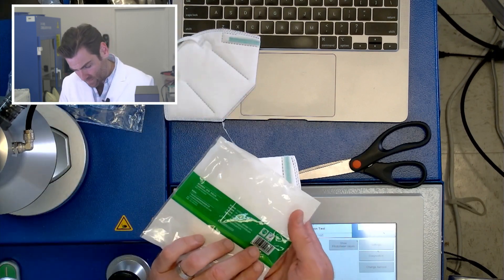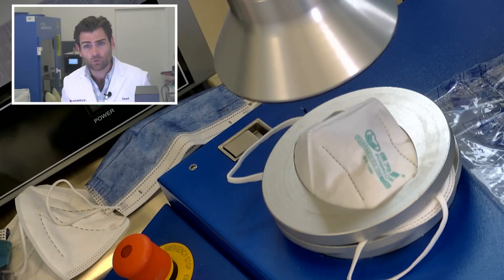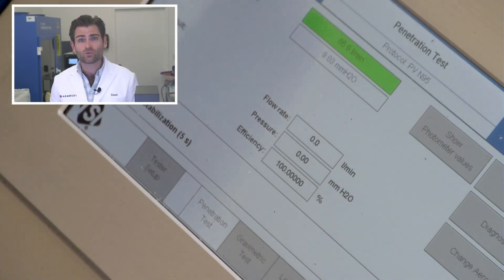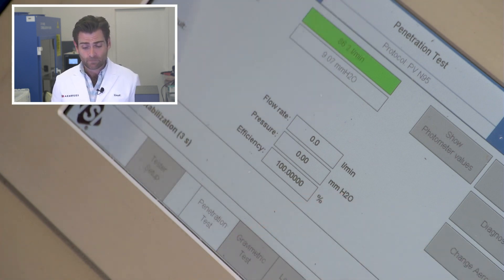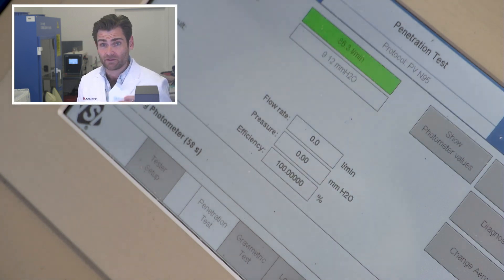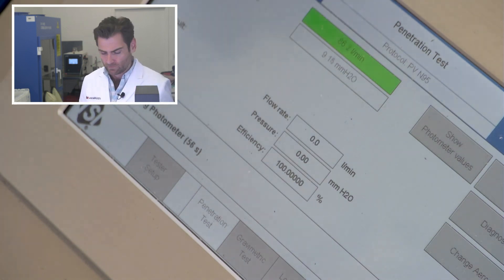I'm not really sure why they opted for the 2006 standard unless this is just really old. We're going to let her rip — this is a PFE machine, a particulate filtration efficiency machine. We're doing the N95 test on this Powecom KN95 to see if it meets N95 standards, which are basically the same thing.